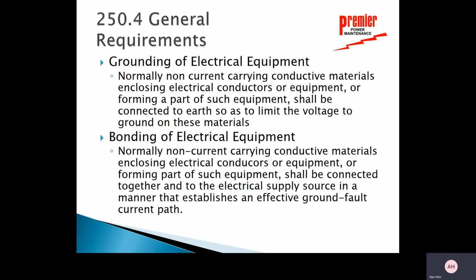Now, this is bonding of electrical equipment. Normally non-current carrying conductive materials, conductors or equipment, or those forming part of such equipment, shall be connected together and to the electrical supply source in a manner that establishes an effective ground fault current path. So this is separate from the neutral, but all of my cases, all of my light fixture boxes, all of my electrical cabinets have to be tied together, returning back to that lone ground connection back at the source. So they're going to be tied together. They're bonded together.